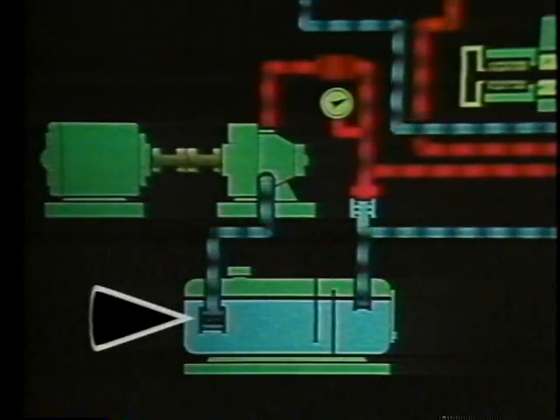At a bare minimum, here's what it takes to get the flow and pressure the cylinder needs to perform work safely: a motor or prime mover to turn the pump, a reservoir or tank to hold the fluid, and the pump which generates flow of fluid into the system. We use a solenoid-operated four-way directional control valve to direct flow to the A port to extend the rod, or to the B port to retract it. To monitor system pressure, we've installed a pressure gauge on the pump output, and to protect the system from excessive pressure buildup, we've placed a pressure relief valve.